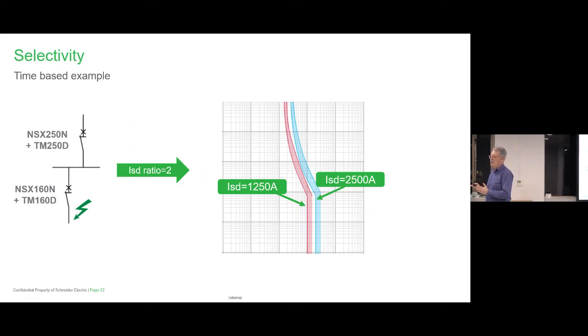Sometimes it's up more than that because we know that boards can be built and requested for withstand of half a second, 1 second, 3 seconds, which is massive. 3 seconds, you don't want that, but there is some like that. But this has to be done under laboratory test. As a supplier and a manufacturer of circuit breakers, we need to say that these two together can work such that they can work with the fault that you're talking about.